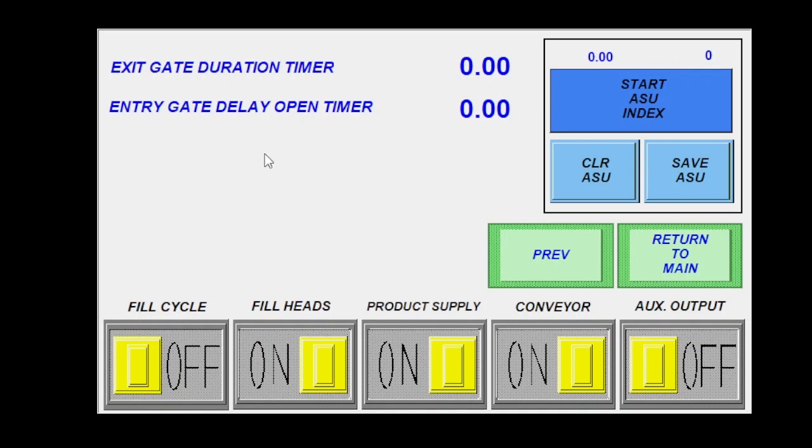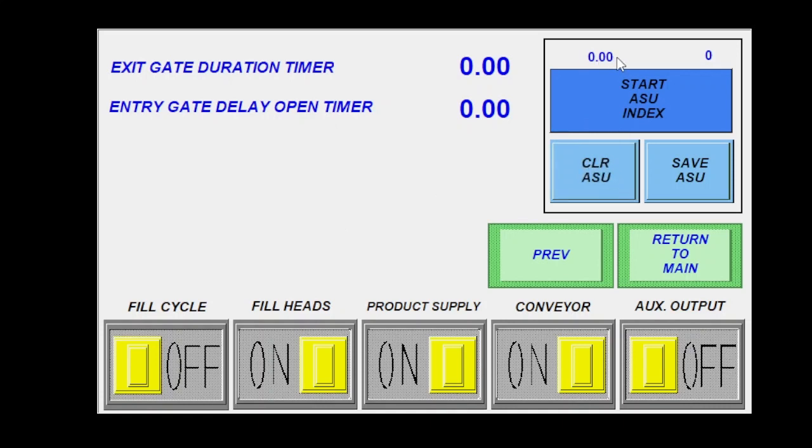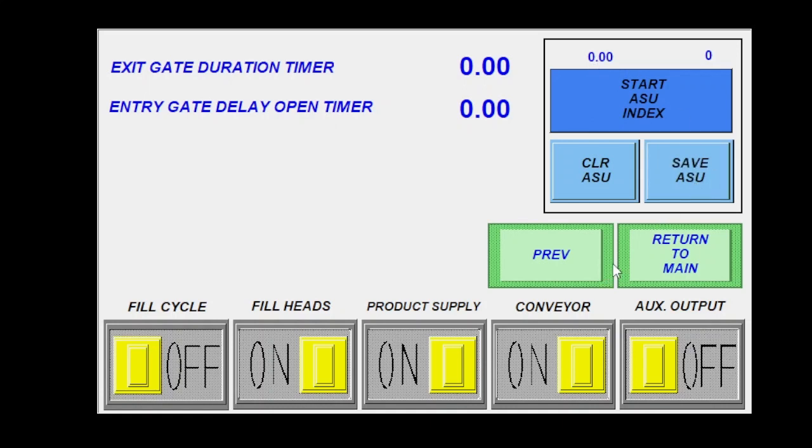And then I would push all my containers up against my entry pin and I would come here, I would clear this. So this is zeros. I want to make sure that under my setup that I programmed the correct number of bottles that I wanted to count, which is normally the same number as the number of fill heads. Once all that's good, I hit start ASU index. It'll do my index for me and then it'll populate a time and I hit save if I'm happy with it and then I'm good to go.